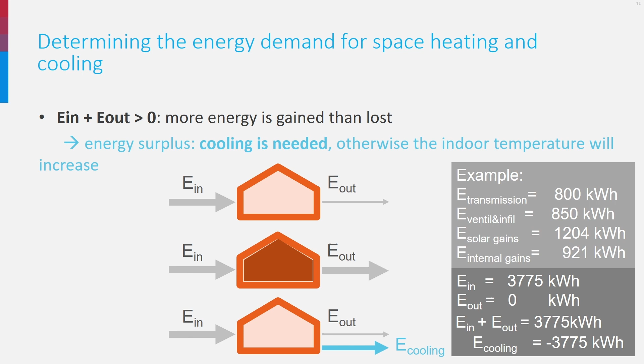If the balance is positive, this means that more energy comes in the building than it leaves. There is therefore a surplus of heat, leading to an increase of the indoor temperature, restoring the balance. If you don't want this temperature increase, you need to remove energy from the system. That is, you need to apply as much cooling as needed to bring the balance to zero, which is what we call the energy demand for cooling. This time we choose a warm hour in the year. Note that the cooling is negative because it is about removing heat from the building.